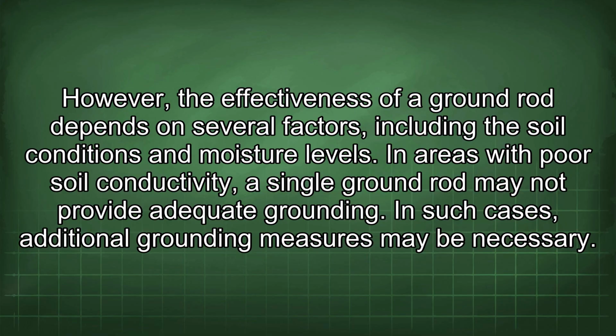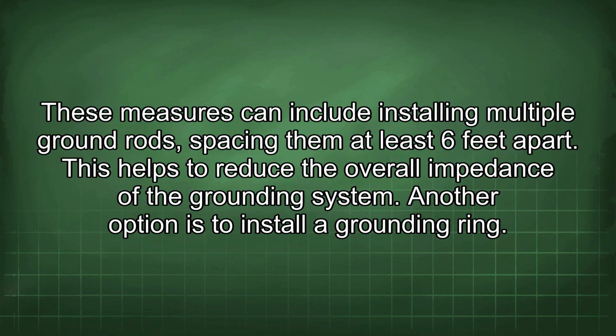In such cases, additional grounding measures may be necessary. These measures can include installing multiple ground rods, spacing them at least 6 feet apart. This helps to reduce the overall impedance of the grounding system. Another option is to install a grounding ring.